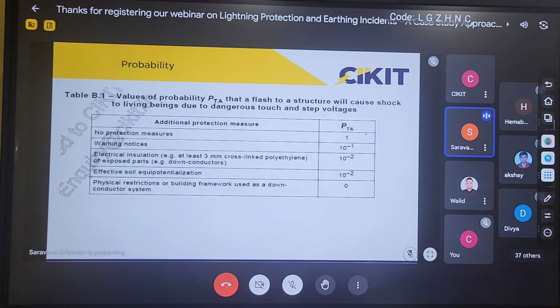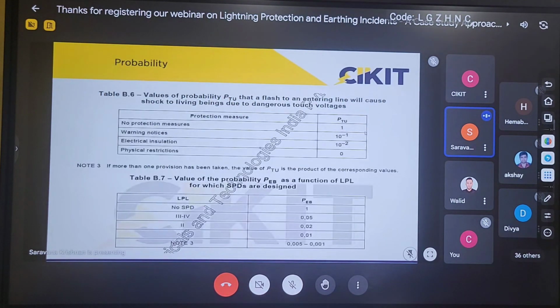So we can observe in the table, PTA, that is flashes to a structure. If lightning is striking on the structure, then both step voltage and touch voltage come into the picture. But if lightning is striking on a power line, then the step voltage won't come into the picture, and only the touch voltage has to be considered. If there are no protection measures, then the PT value will be 1. Similarly, if I have a warning notice, the value becomes 0.1. If it is electrical insulation, 0.01. And if it is physical restrictions, it becomes 0.